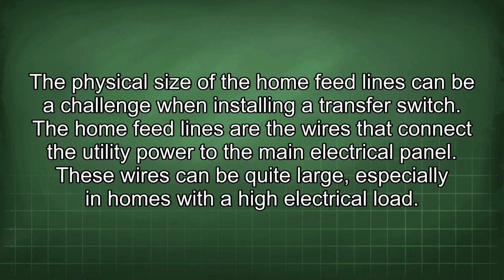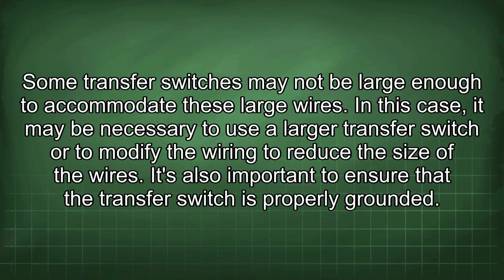The physical size of the home feed lines can be a challenge when installing a transfer switch. The home feed lines are the wires that connect the utility power to the main electrical panel. These wires can be quite large, especially in homes with a high electrical load. Some transfer switches may not be large enough to accommodate these large wires. In this case, it may be necessary to use a larger transfer switch or to modify the wiring to reduce the size of the wires.